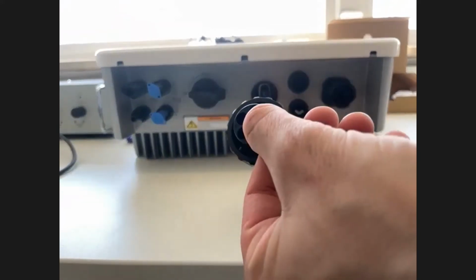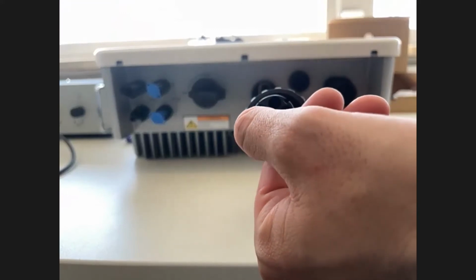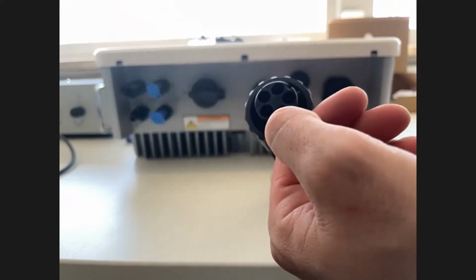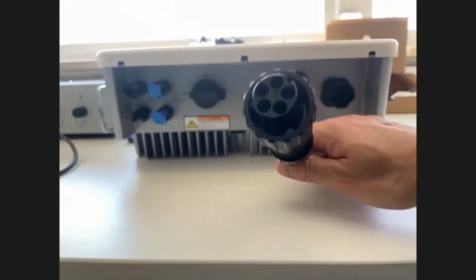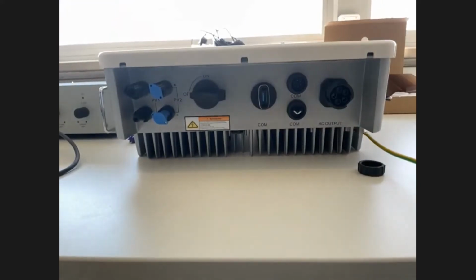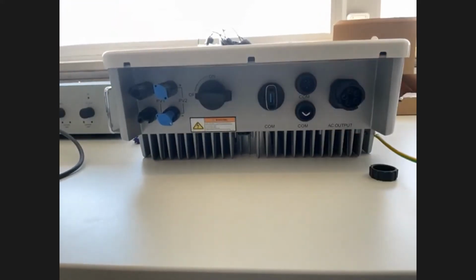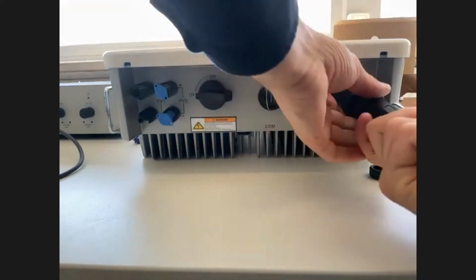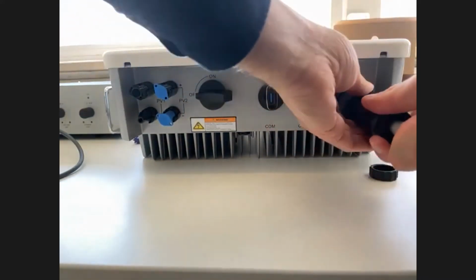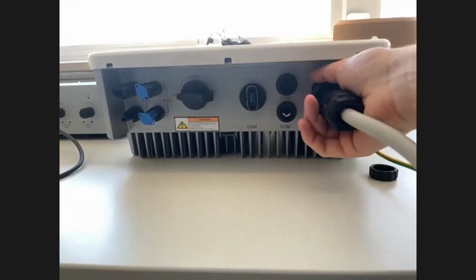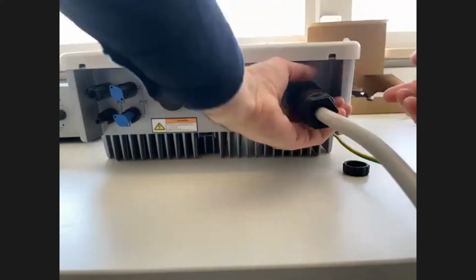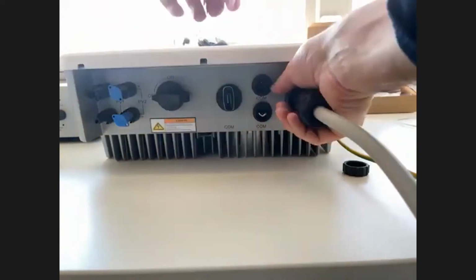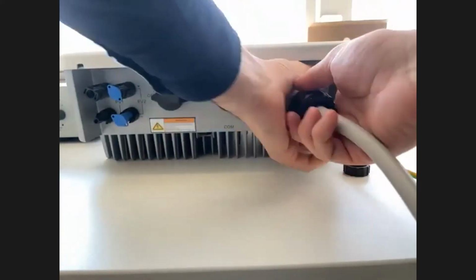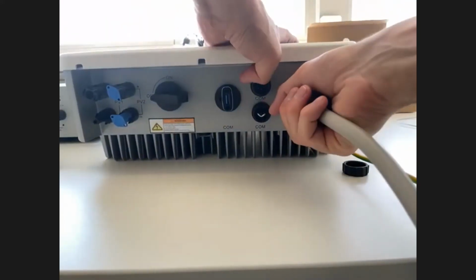But basically here you also see the numbers, the neutral, the PE, the line 1, line 2, and so on. But when that's all done, then you just connect it here to the AC out, and then just tighten this one here. And it says you can feel a little bit of a click, and then it's tightly fastened.